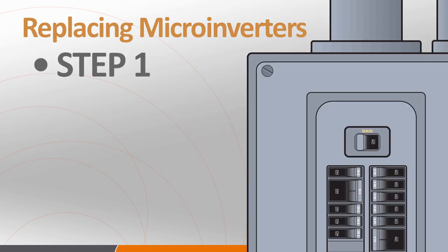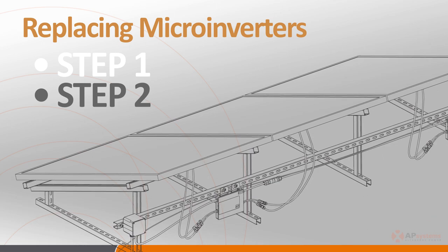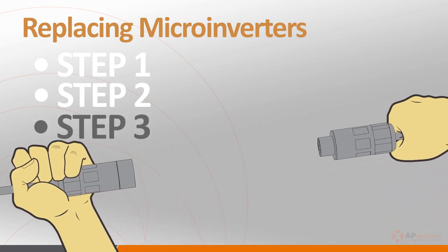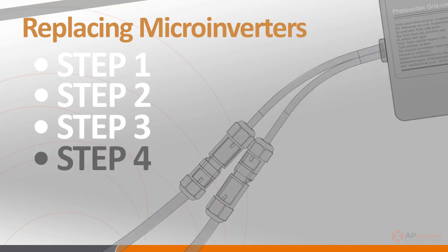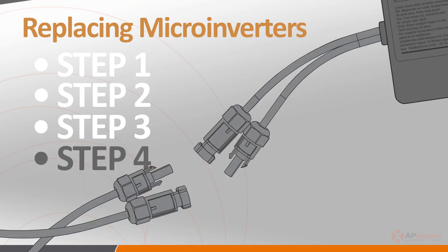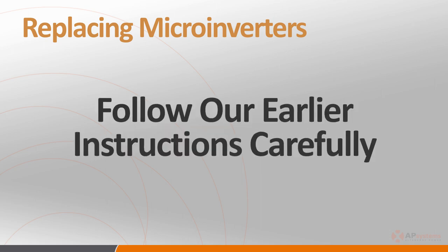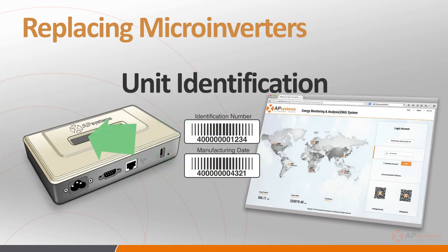To remove an inverter, follow these steps. Step 1: de-energize the AC branch circuit by turning off the branch circuit breaker. With the branch circuit offline, cover the PV modules associated with the inverter to be removed with opaque covers, ensuring the panels are not producing DC power. Next, disconnect the AC connectors to the adjacent inverters. Step 4: disconnect the DC connectors from the PV modules associated with the inverter. And finally, physically remove the inverter from the rack. Follow the installation procedures covered earlier to install the replacement inverter, making sure to change the inverter UIDs in the ECU and EMA to reflect the changes you've made.